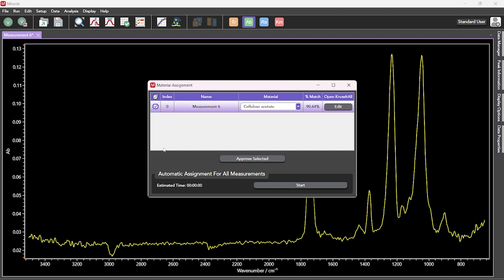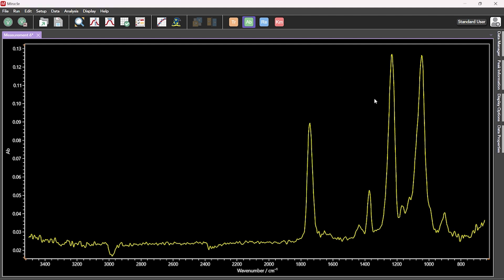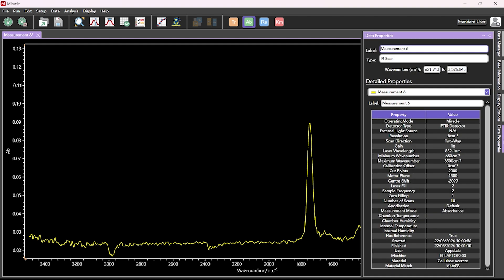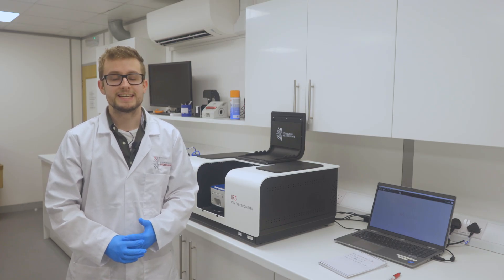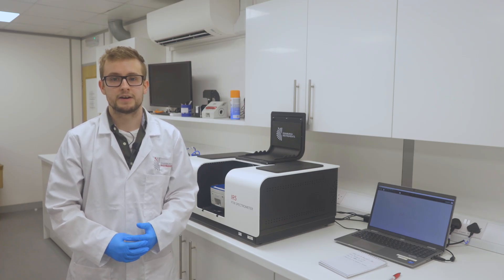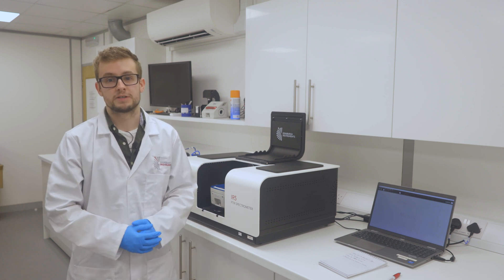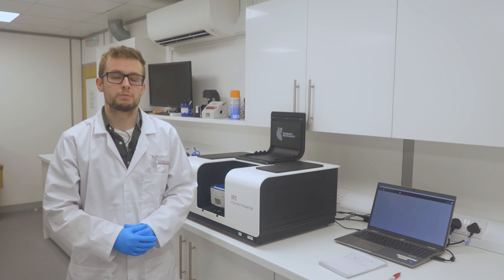The material assignment window can now be closed. The material assignment along with the percentage match are stored in the data properties section for future reference. In this demonstration we've shown how materials can be simply and easily identified using an IR5 spectrometer along with KnowItAll, the optional upgrade to Miracle. Thanks for watching.